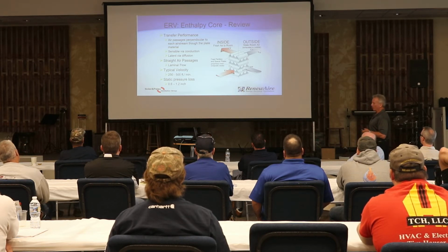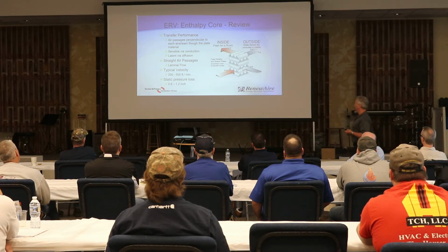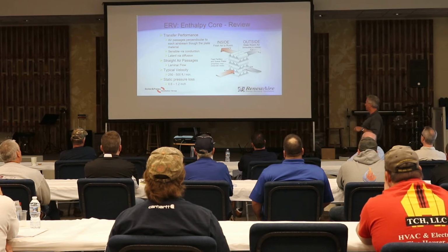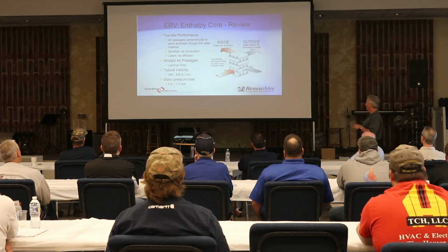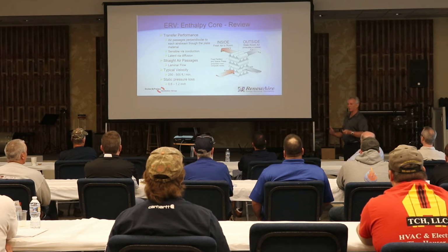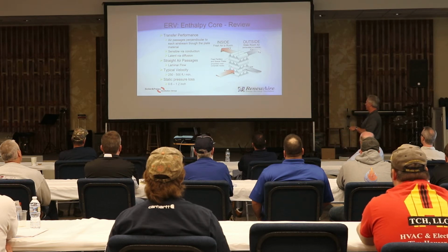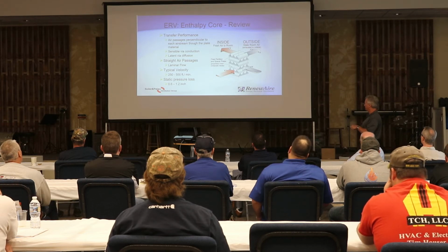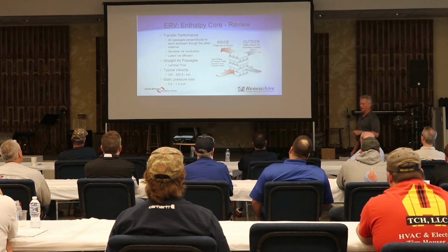Now, enthalpy cores, on the other hand, are completely different. What we're doing here is very similar to what an HRV does, with a significant twist. We're exhausting room air through an air passage, separating that air passage from a perpendicular or opposed air passage with this thin plate. When we say static plate, fixed plate heat exchanger, this is the plate we're referring to. So you've got two opposed air passages, and both sensible and latent heat will transfer through that plate.